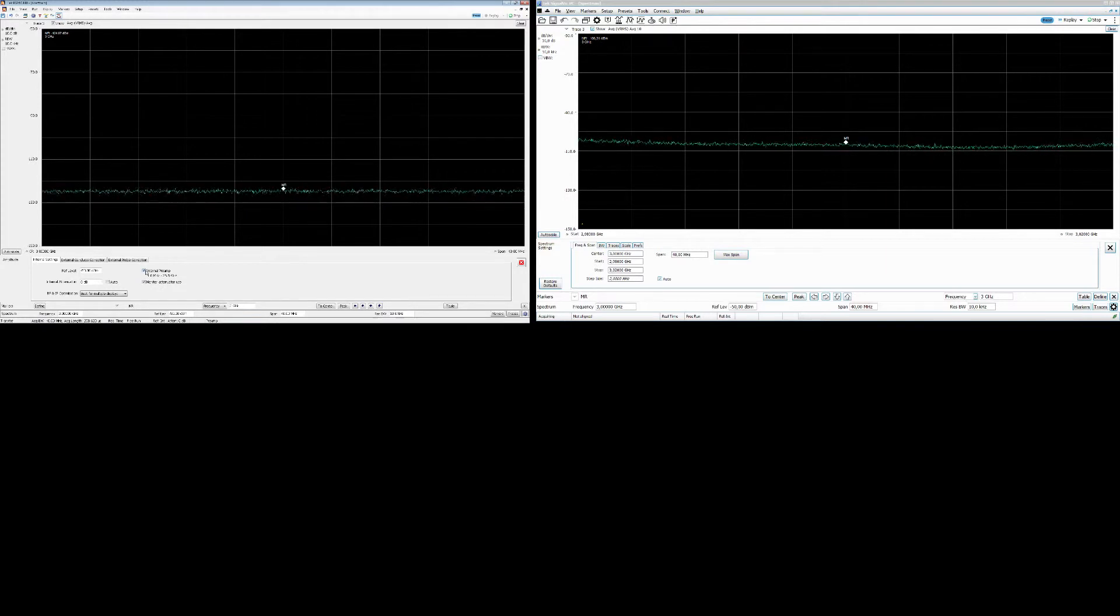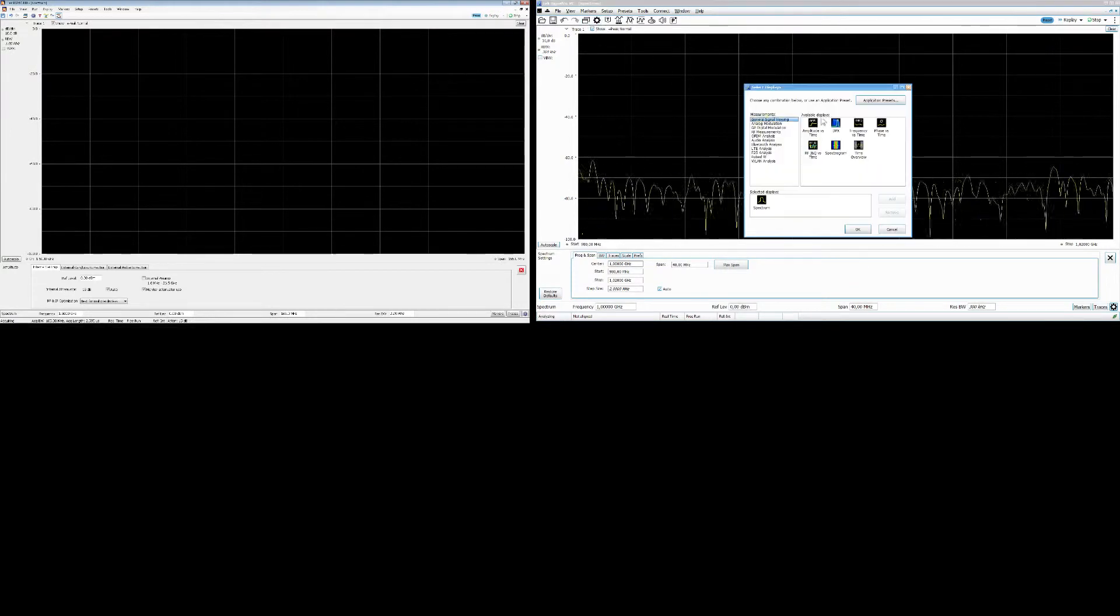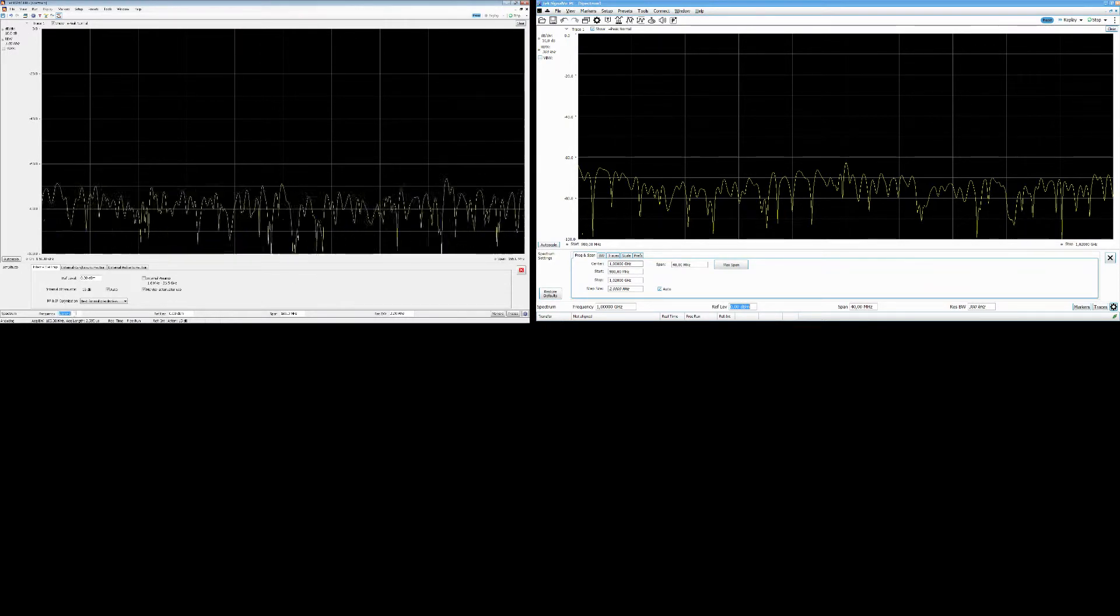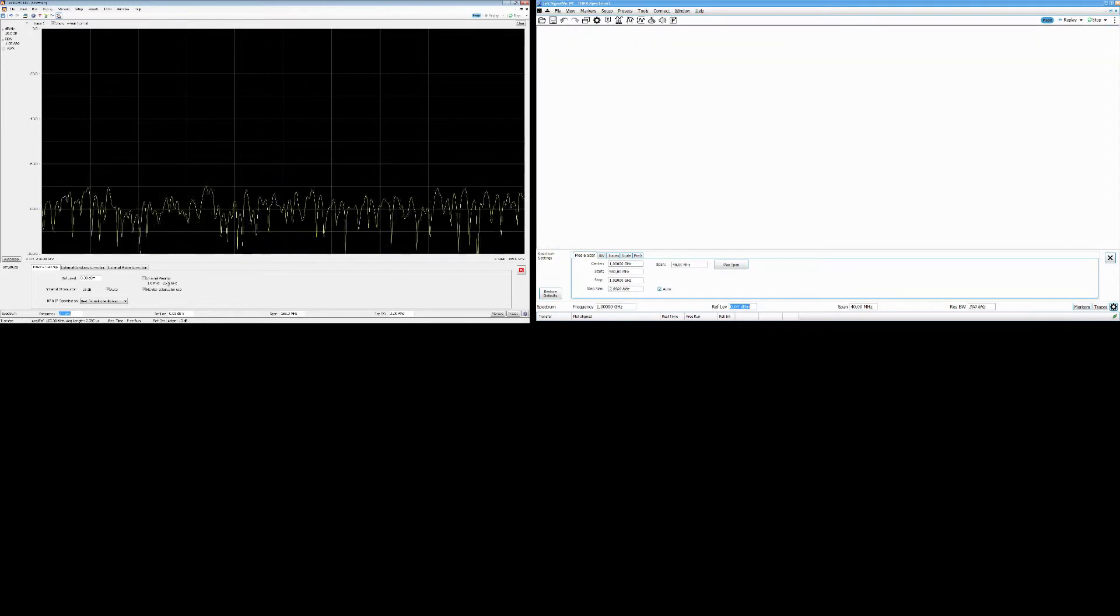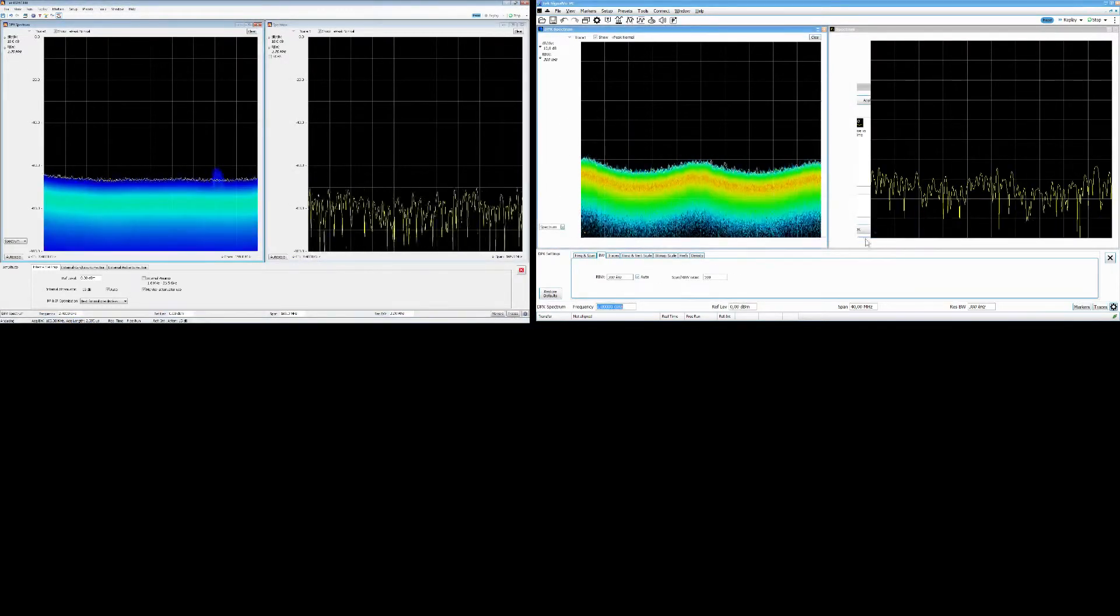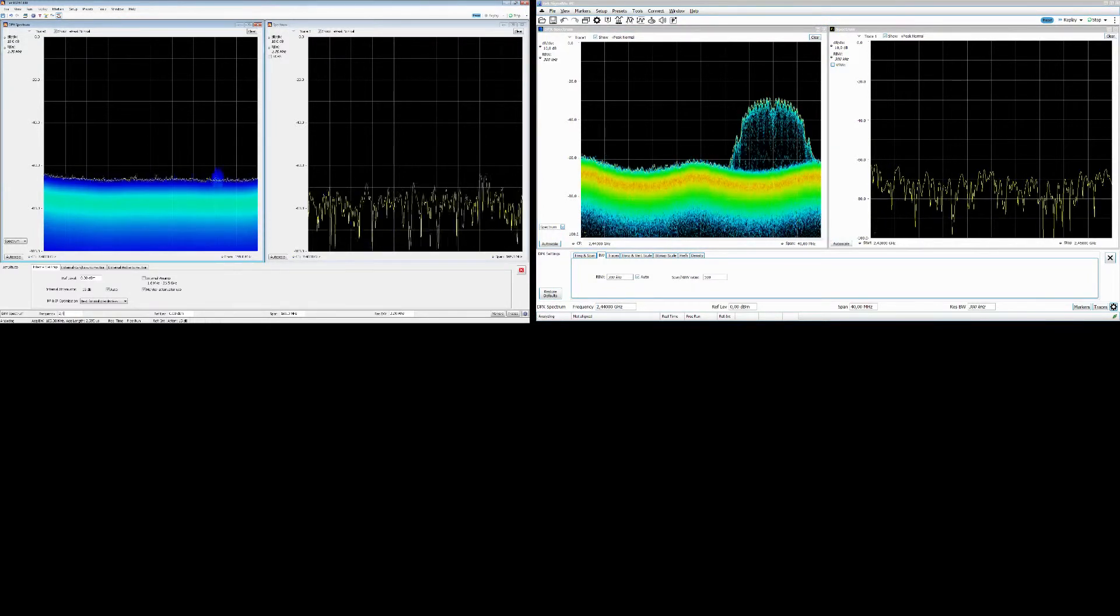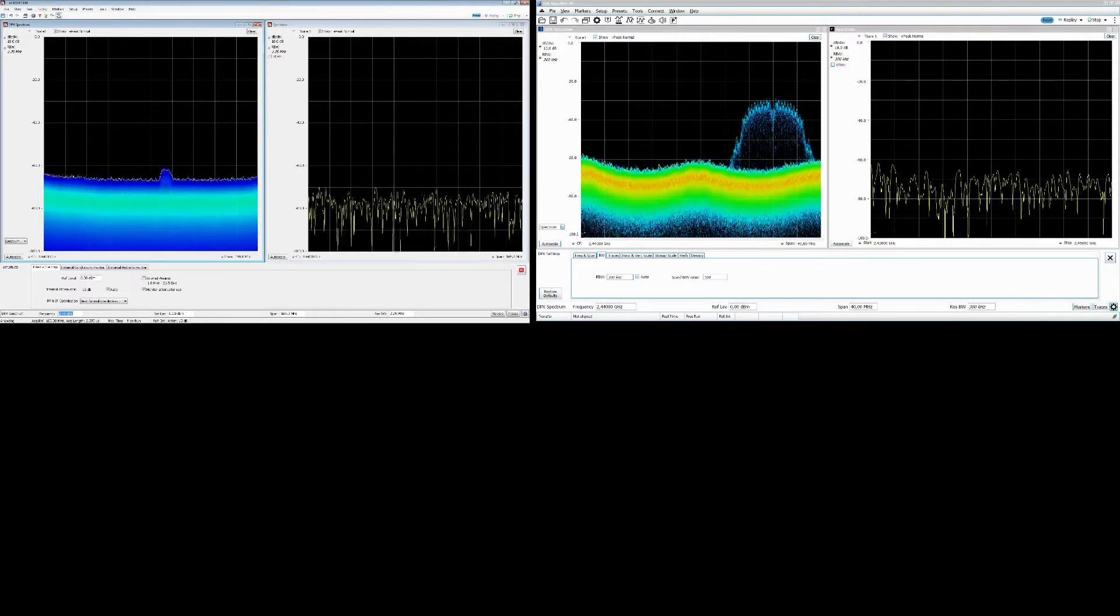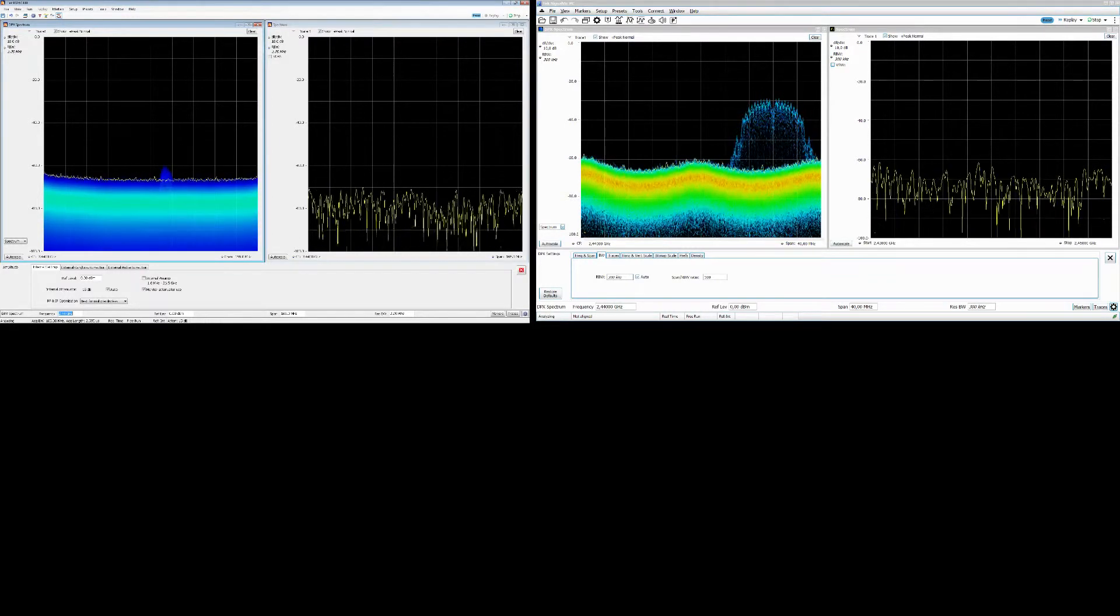But now let's start with some fun stuff. You can see the difference. The next difference is actually how fast it is in DPX mode. So we'll go with this one and do DPX. For sure I will just change the center frequency to 2.4 gig. And I will do the same here if it wants, if it lets me. Yeah, it's a bit slow. 2.4, I'll go with this one, DPX, here you are. And there we are, 2.4 gig is exactly where we want to go.